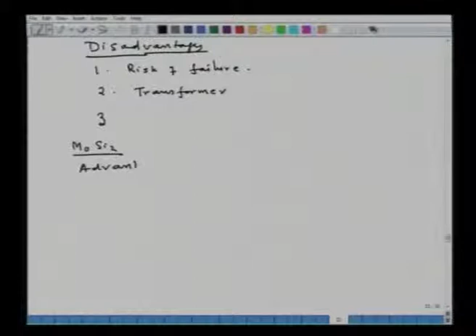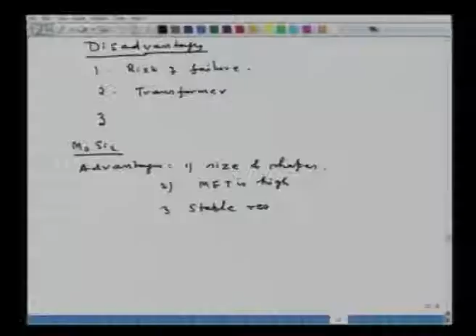Another one, molybdenum disilicide, advantages: again available in a variety of sizes and shapes, almost all sizes and shapes are available. Most important advantage is that their maximum element temperature is very high, and as a consequence the furnace can be operated at high temperature. Third, stable resistance, that is old and new molybdenum disilicide elements can be joined in series.